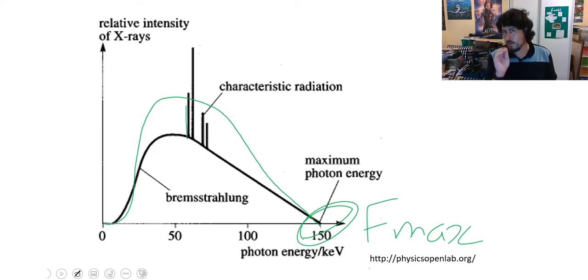Note also that we have not changed the metal target. So the characteristic x-radiation peaks need to stay exactly where they are. The only time that will change is if you change the target metal.